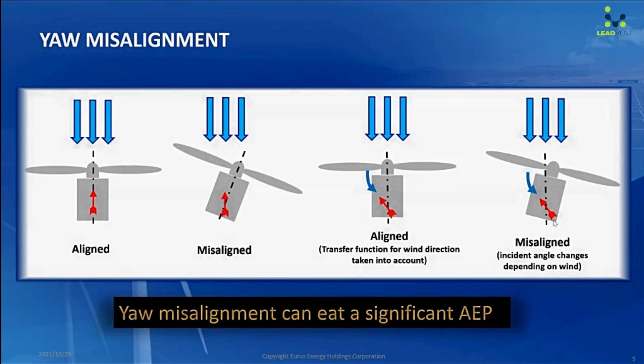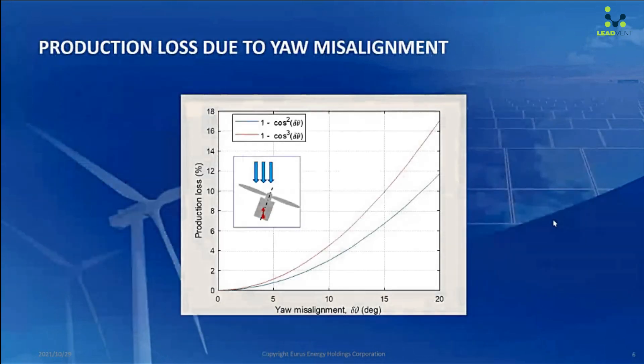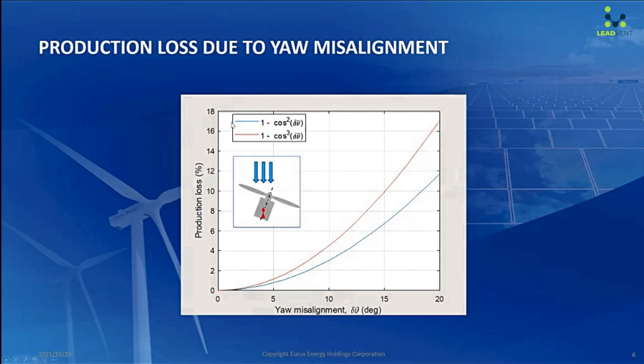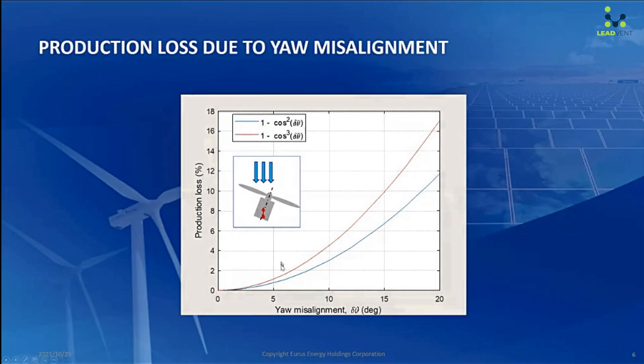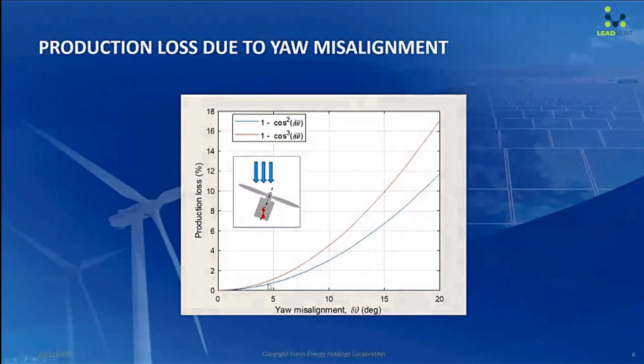This misalignment can eat a significant amount of AEP — it can be a few percent. This is a quick calculation of how much loss to be expected due to yaw misalignment. The vertical axis is the production loss and the horizontal axis is the misalignment angle. It's said that this production loss follows cosine squared or cosine cubed. Many turbines have a four-degree misalignment, in which case we may be losing around one percent of production.